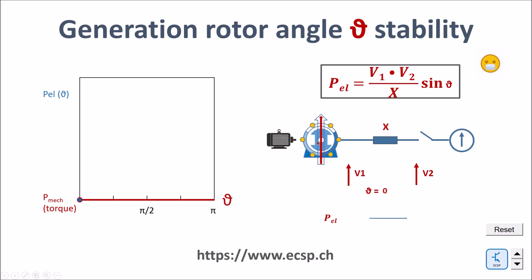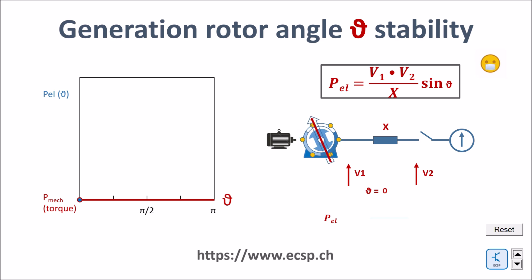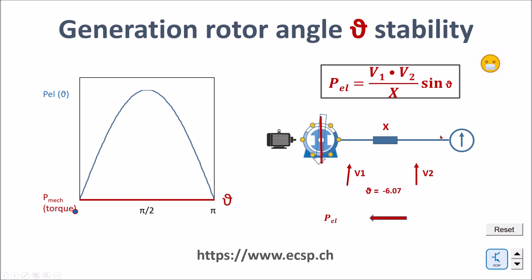As long as the generator is disconnected from the grid, the rotating magnetic field through the stator is only induced by the DC magnetic field from the rotor. This means there is no angle between the rotating magnetic field of the stator and the rotating magnetic field from the rotor, so the angle theta is equal to zero. Let's rotate this rotor — the rotation speed is for 50 Hz and you see that the two arrows are sitting on each other.